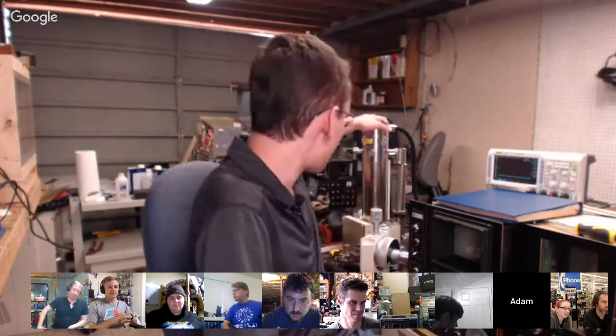It's not changing the scintillator that caused the vacuum leak, because I currently have the entire scan column capped off, and it's just the valve body. So I've isolated the leak somewhat, which is good, but it's still going to be probably a couple more hours of troubleshooting to get that leak fixed. So watch the live stream for that.